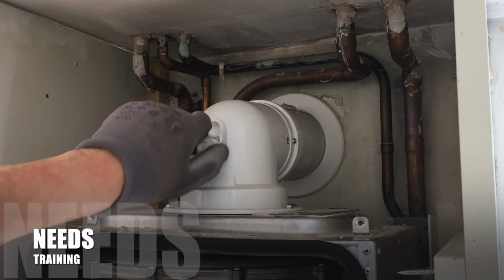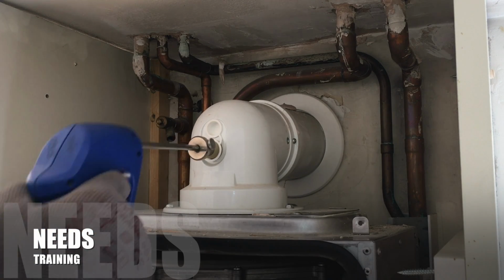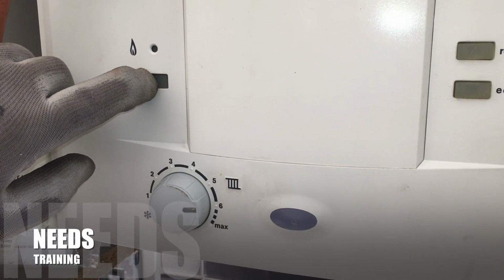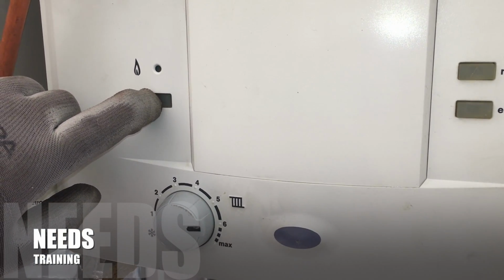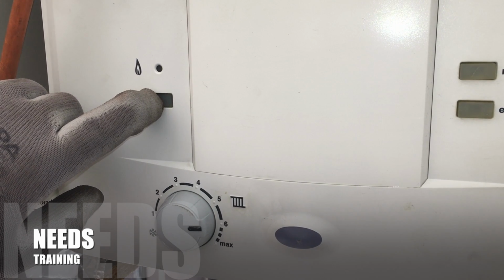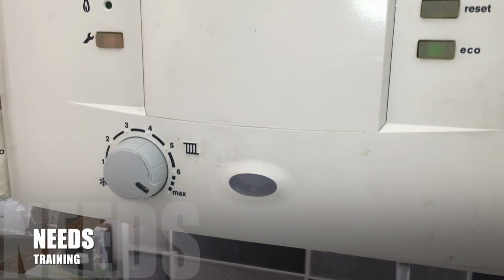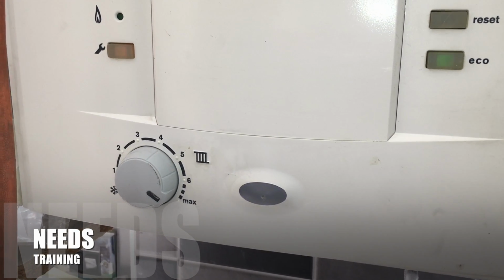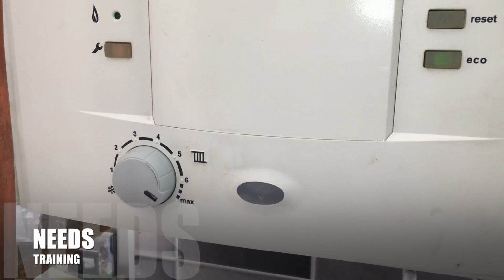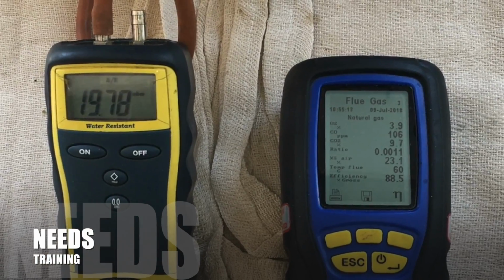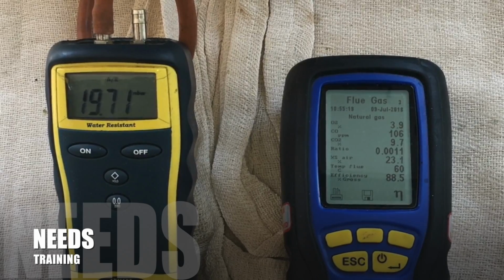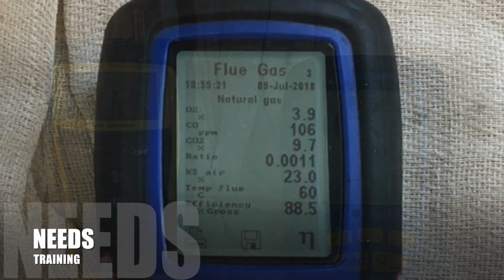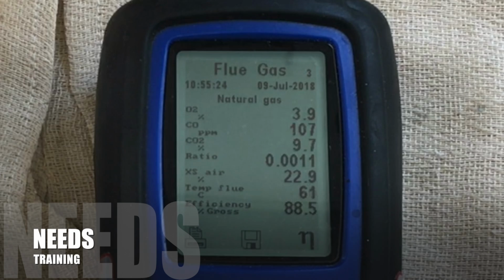Put the flue gas analyzer probe into the flue test point. Push the spanner button to enter engineer's mode. The orange light will appear. Turn the heating controls to max. Using a gas manometer and a flue gas analyzer, you can now check gas input pressure and if the CO2 readings need to be adjusted.